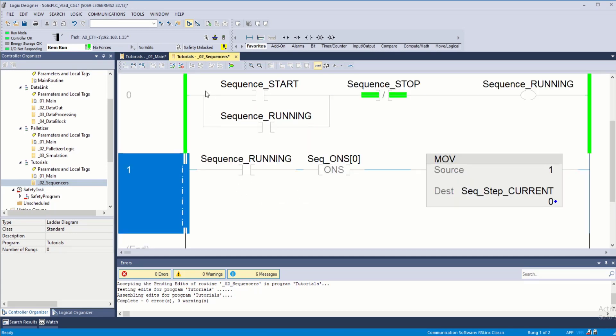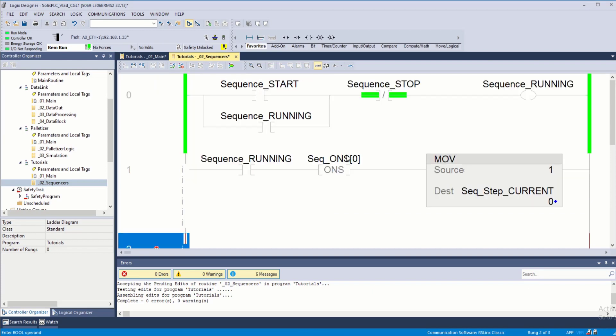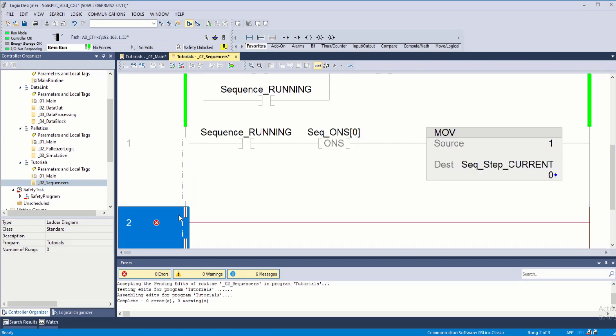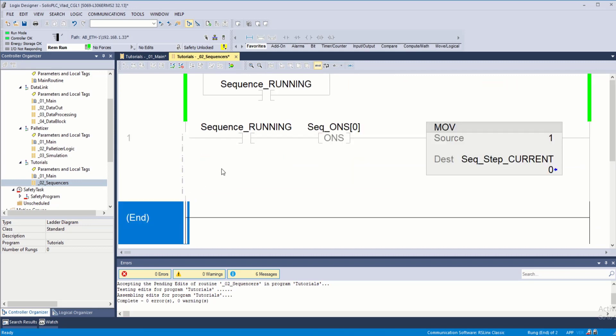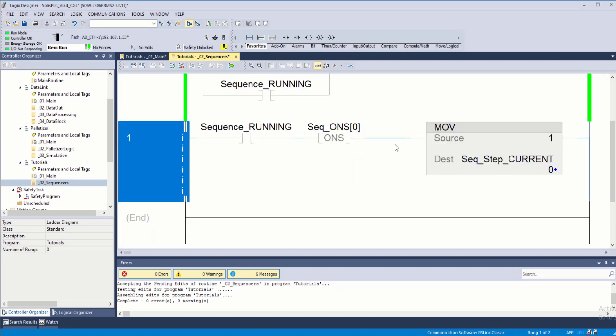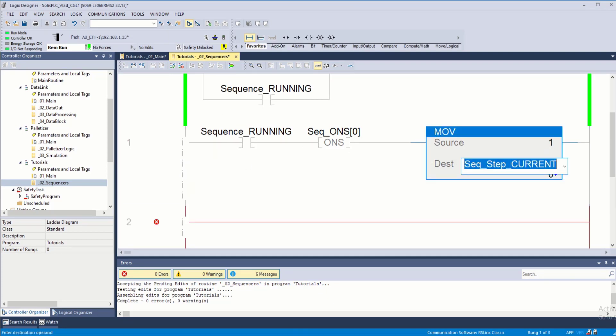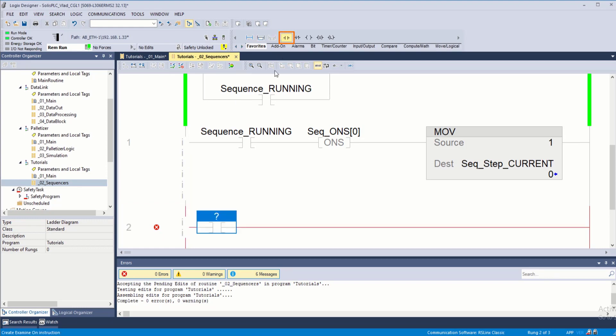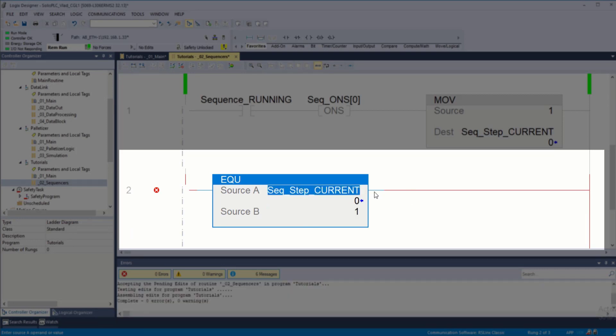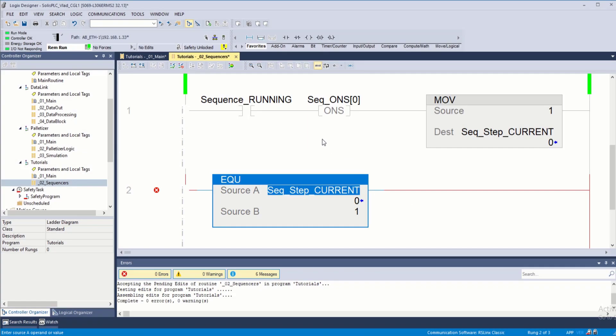I'm also going to add a rung that tells me when we get to the end, we can pause the sequence and reset this back to zero. At this point the sequence is in step one, so I can have a step one condition which is essentially an EQU — if the current step is equal to one, we're going to execute a certain condition.